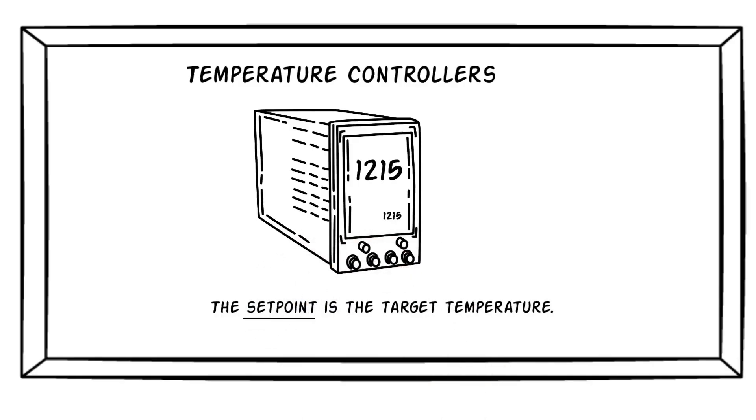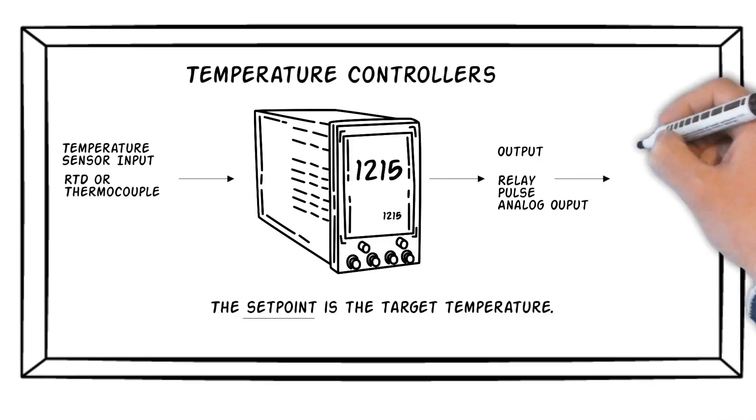For a temperature controller to function, it must have a temperature sensor input. And the most common types of industrial temperature sensors are RTDs and thermocouples. A controller must also have at least one output. The output may be a relay, a pulse output, or an analog output. The output is connected to a control device such as a heater, fan, or valve.